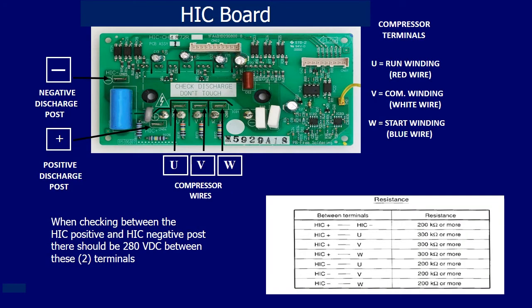When checking the HIC board, remove the red, white, and blue wires to the compressor and also the gray and yellow DC supply voltage wires. As reflected in this illustration, a reading of 200 k ohms or more should be present when checking from the positive and negative post back to terminals U, V, and W.